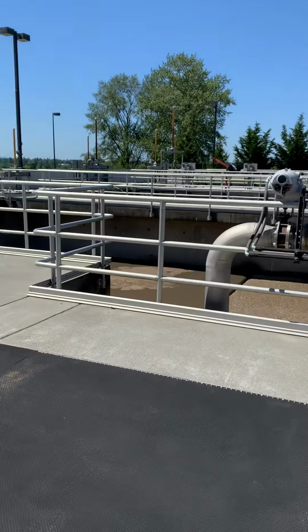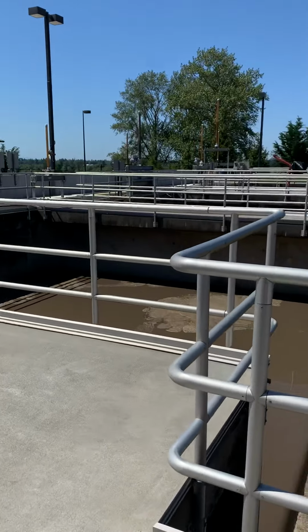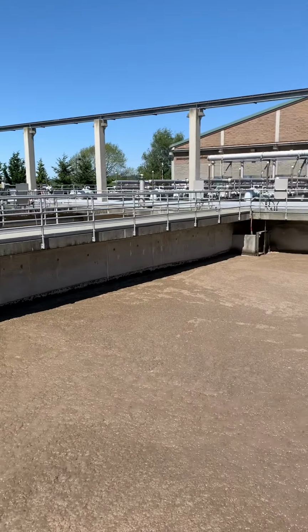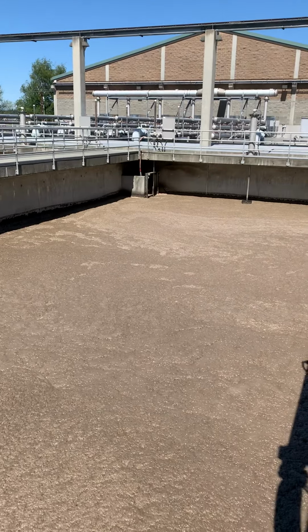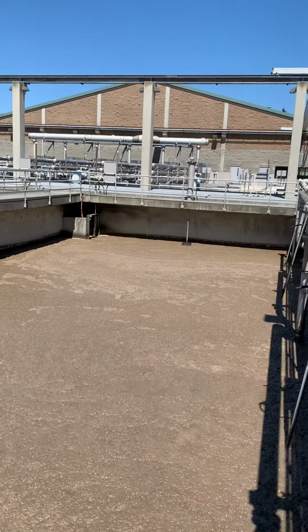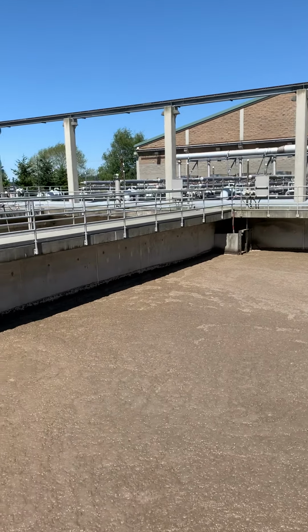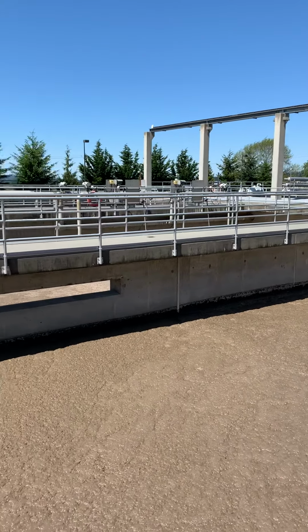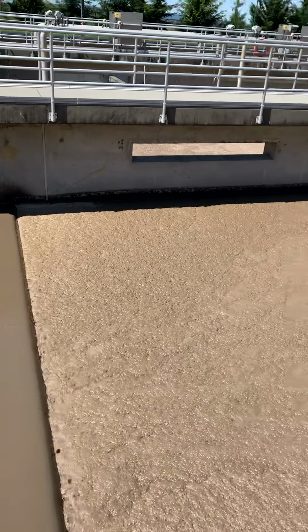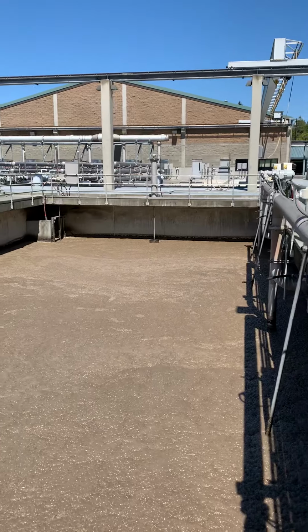So how, you may ask, do we get the non-soluble solids and the dissolved solids out of the wastewater? Well, we have our biomass here. We're running 2 basins out of 3 right now. We have two anoxic zones and 3 oxic zones. They're separated by walls. You can't really see the walls because they're submerged. I won't go into that part of the biology and chemistry right now. But needless to say, we maintain a population of beneficial organisms, bugs, we call them bugs, that stabilize the wastewater.